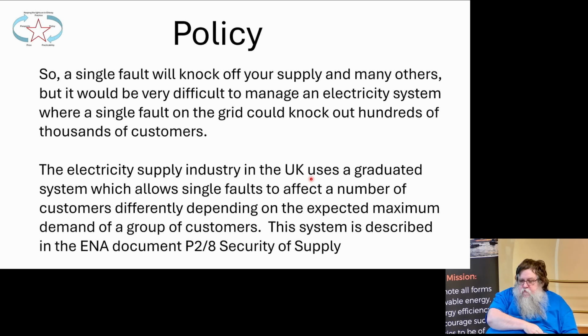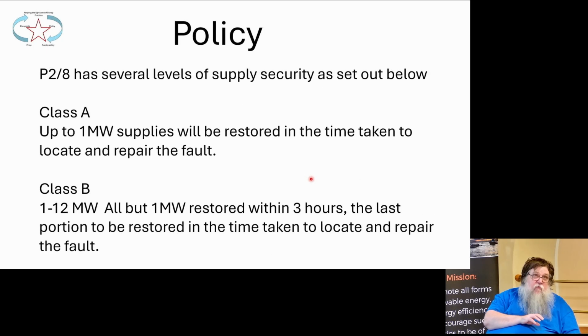So while we accept that for up to 1 megawatt, if we did it for the whole of the electricity system that we had no backup. Say we got the one cable to Orkney that was there for many years, failed, and we had to wait till that was repaired, and it took 3 months or 4 months to repair. You can't afford to have folks in Orkney with no power for 3 or 4 months. So there's a graduated system set out under a document called P2/8, Security of Supply, and it says how long the DNO have to be able to repair or to ensure that the power doesn't go off even after the fault and so on. And I'm going to go through those things now.